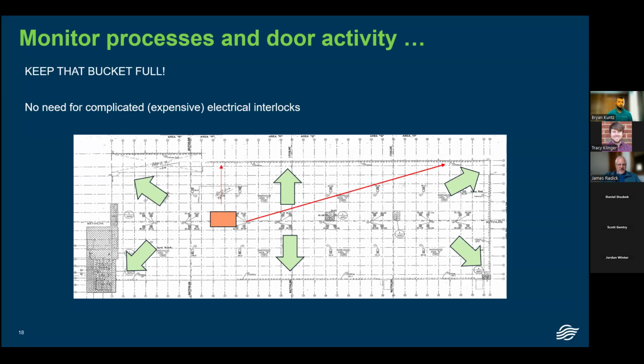pressurization does something else for us. Okay, it allows us to monitor processes and door activity. We want to keep the bucket full, if you will. When we're trying to achieve a positive pressure in the space, and I'm going to go more into the benefits here momentarily, the green arrows are just illustrating a positively pressurized vessel or a building that has equal pressure throughout. And the orange rectangle is illustrating an air handler. Now, if you've got something pressurized, it doesn't matter how far that door is that opens, or that exhaust process that could be illustrated by the short arrow that's pointing upwards on there. Is it that close to the air handler?